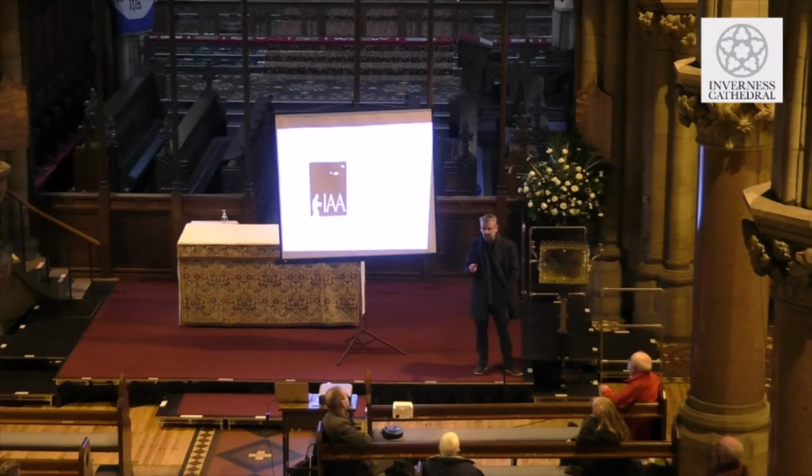Well, I'll come to that. I'll just finish my point about that, and then I'll talk about this building, because I've done a zero carbon strategy for the cathedral. So, issues to do with air source heat pumps and technology. There's always a lot more in it. As I say, there's no silver bullet. There's no technological solution. All of these issues are interrelated. So, for example, air source heat pumps only bring the water up to 55 degrees. So if you've got a big community hall and a large water tank, you've got to add more energy into that because you need to bring the water up to 60 degrees to kill Legionnaire's disease. So there are complex issues.